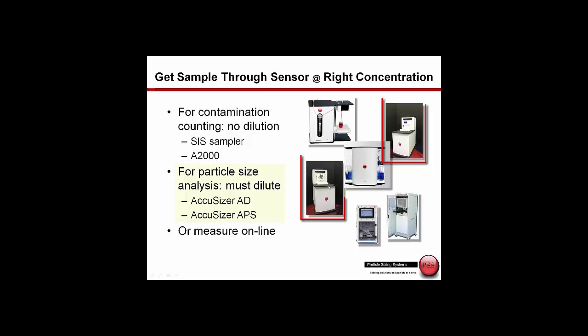The two systems here, the AccuSizer AD and the AccuSizer APS, have automatic dilution systems, either a single stage or a multiple stage. Here we can take very highly concentrated samples, automatically dilute it into that optimum concentration range for the sensor, and perform the particle size analysis and get the particle count still accurately in particles per ml. This can be done in the laboratory, or in the lower right, we show the online versions of the AccuSizer that can work with any of these sensors and can be used in the process environment.